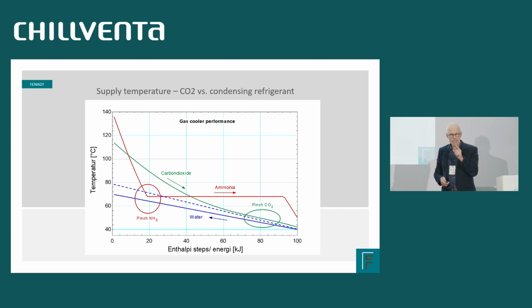It's one of the points you should remember from my presentation: district heating network temperatures, cold return, cold return, cold return. The reason is that when we need to heat water with CO2 as refrigerant, we are cooling the green curve with CO2, and the lower you get in this corner, the better COP you have. So entering the heat pump with a low temperature is very important.